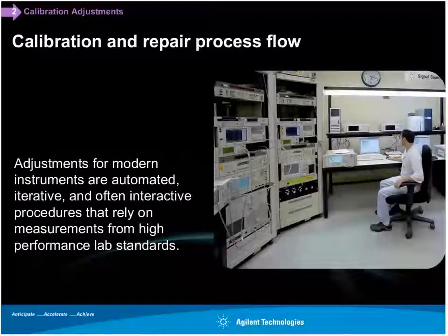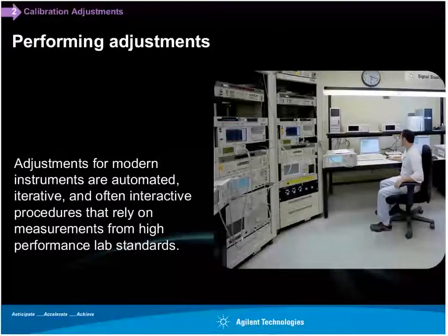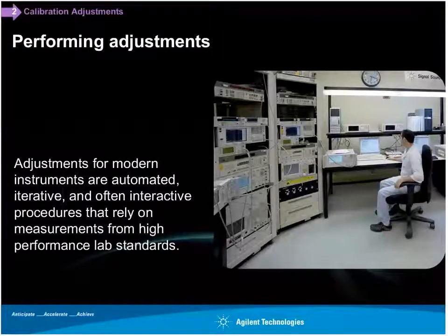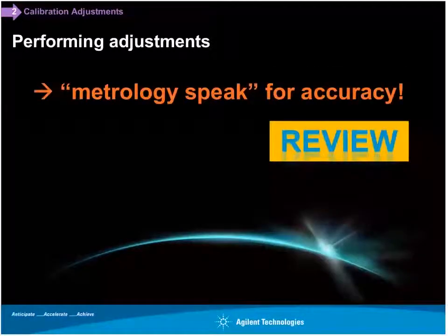So maybe the one point to repeat on adjustments was, for modern instruments, those adjustments are automated, they're iterative, oftentimes they're interactive, they move, they branch around, and they require external instruments. Here you see one technician running 2 different stations that are doing adjustments. And they can take several hours on some of our highest performing instruments.